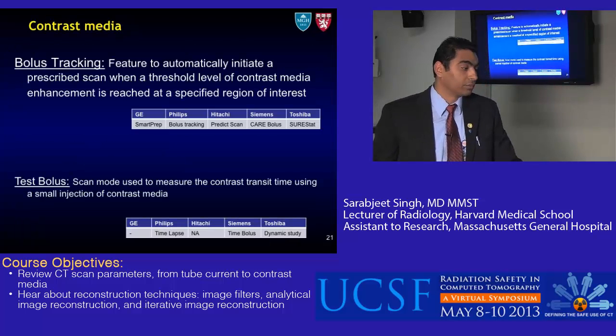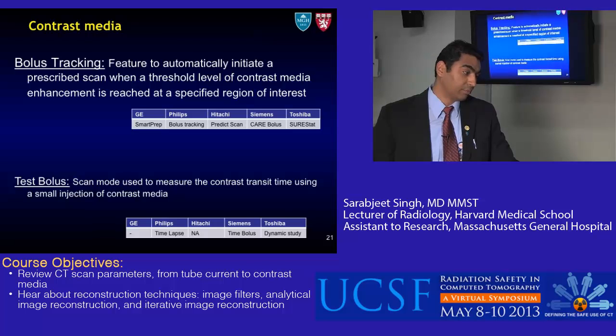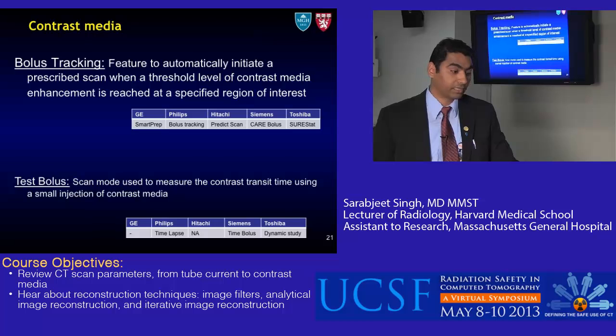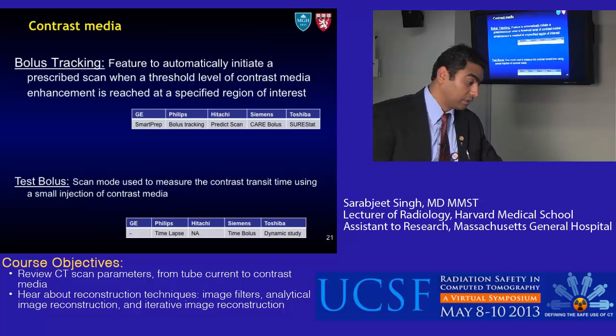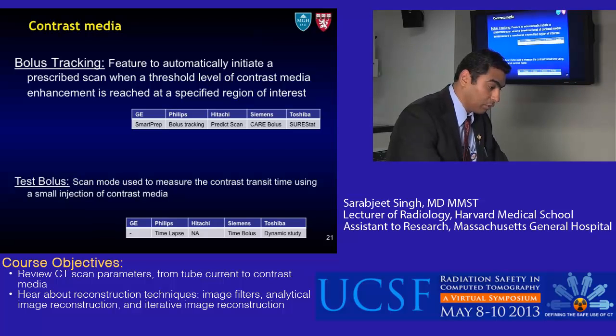A few parameters for contrast media: bolus tracking is a feature that automatically initiates a prescribed scan when a threshold level of contrast media enhancement is reached at a specified region of interest. GE calls it Smart Prep, Philips calls it Bolus Tracking, Hitachi calls it Predict Scan, Siemens calls it Care Bolus, and Toshiba calls it Sure Start. The test bolus is a scan mode used to measure contrast transit time using a small injection of contrast media. Philips calls it Time Lapse and Siemens calls it Time Bolus.